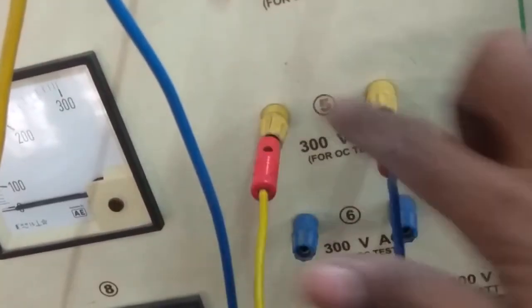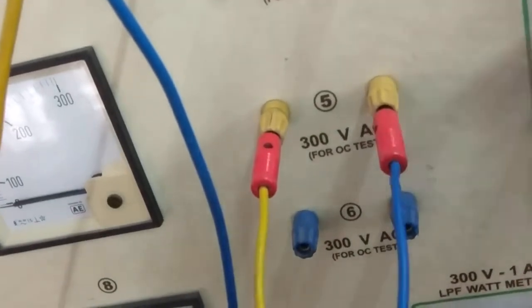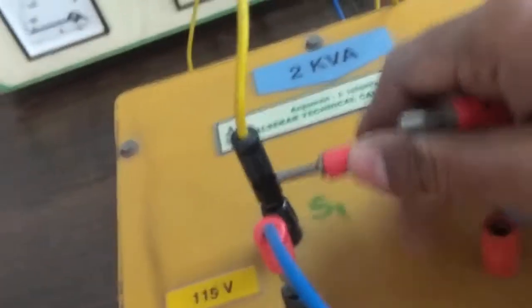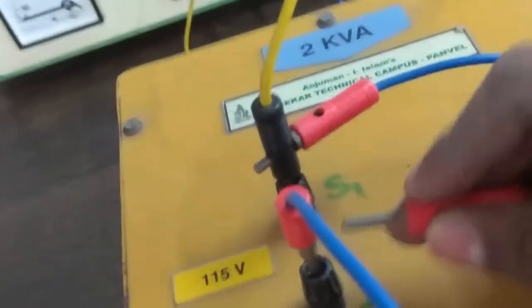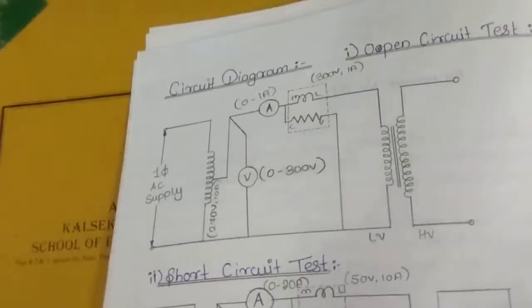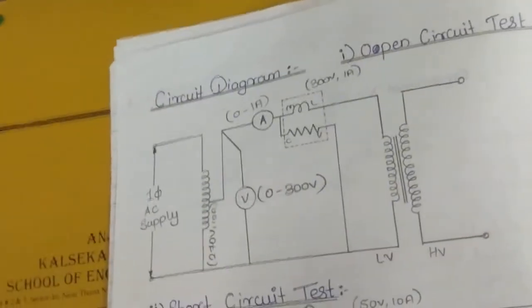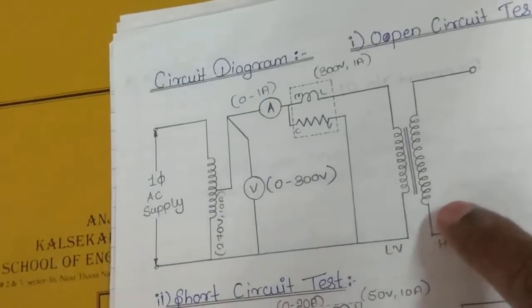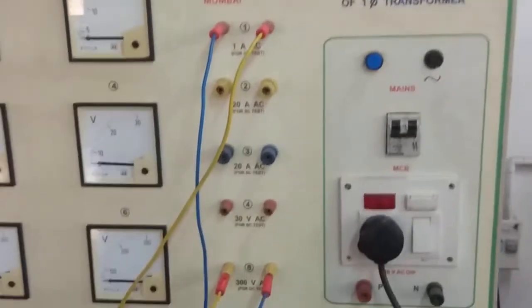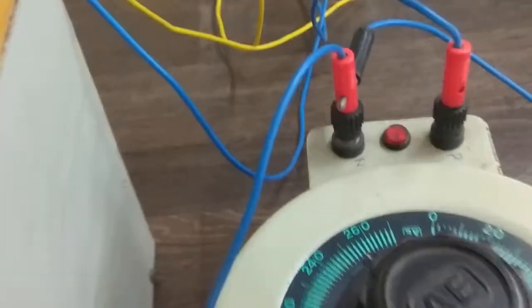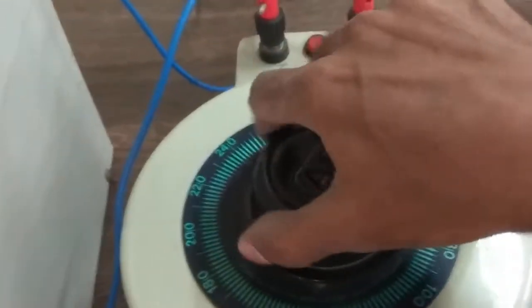Now we will connect the voltmeter in parallel to the LV side of the transformer. Now we have done the connection of the open circuit test. As per the given circuit diagram, we have completed all the connections. You can see it clearly. The supply is given to the variac and from the variac to the transformer via voltmeter, ammeter and wattmeter. Before switching on the supply, we will keep the variac at the minimum position.